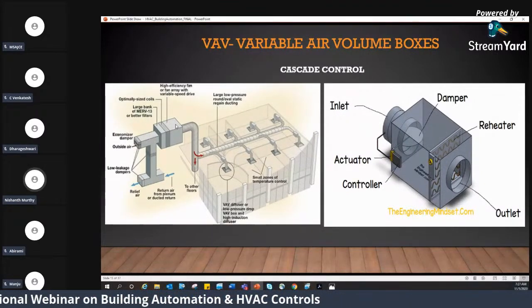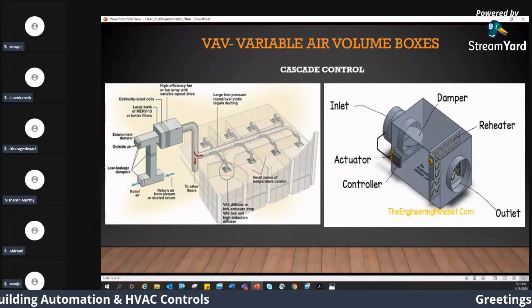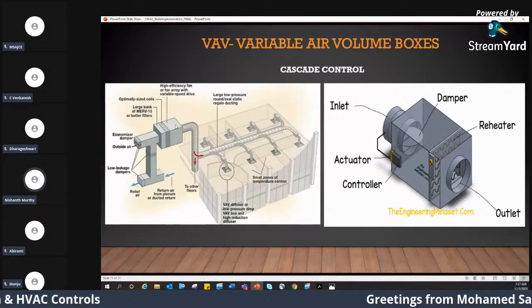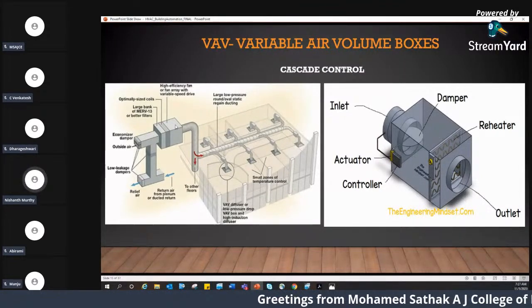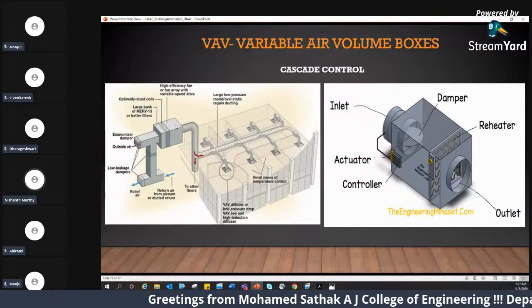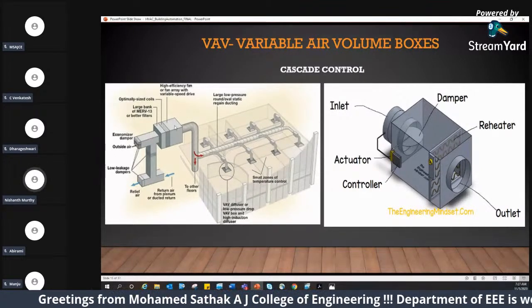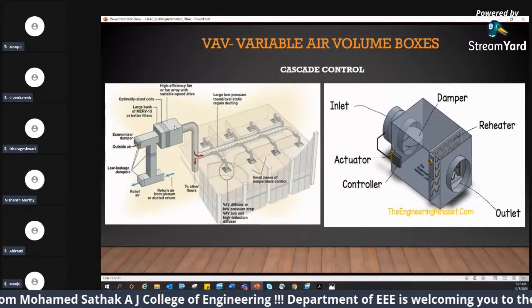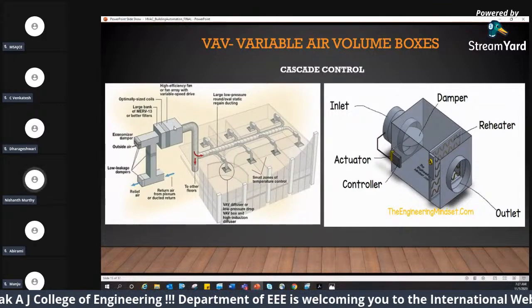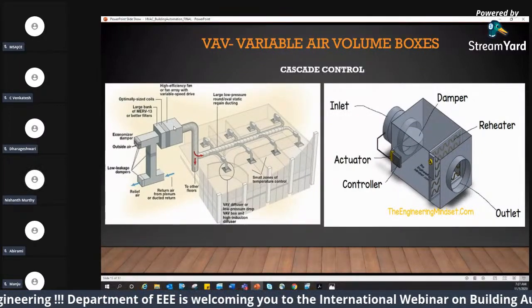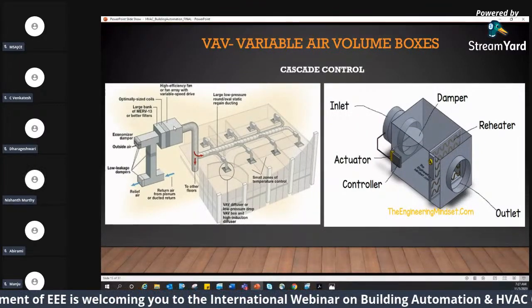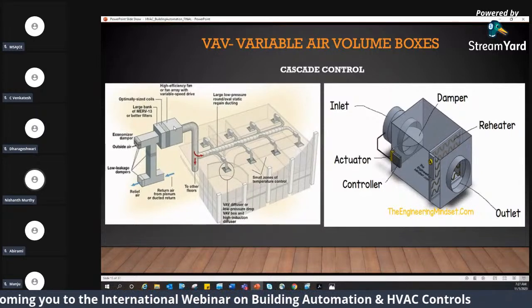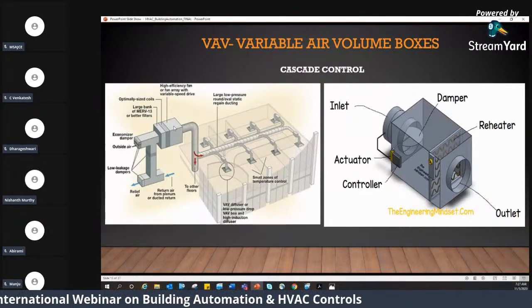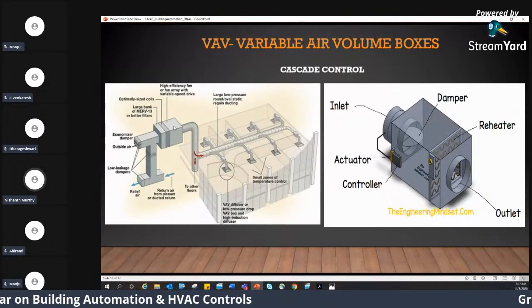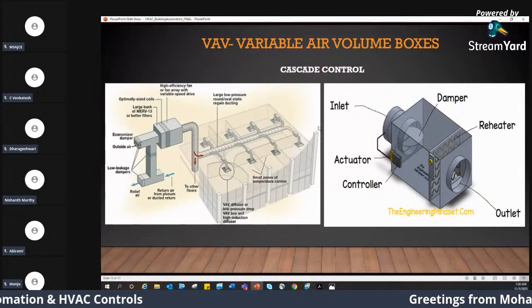Okay, so if the damper is closed, there is no airflow. So when you're too cold, you'll switch off the fan, and the damper will close automatically. When it's too hot, you'll put it at full speed, so the damper will open automatically. The damper operates just like a window. You open, you close. So the damper modulates accordingly to increase or decrease the temperature in the room. It's actually controlling the airflow, which affects your temperature. That's what we call cascade control, controlling your temperature by controlling your airflow.